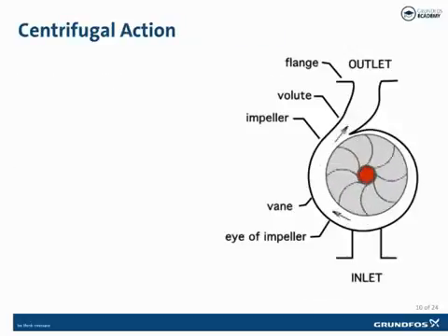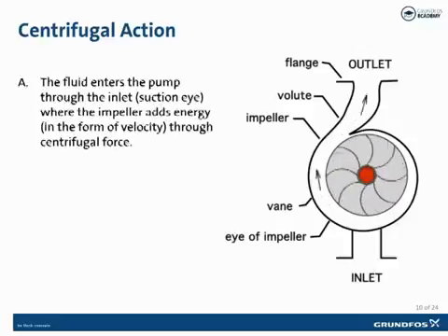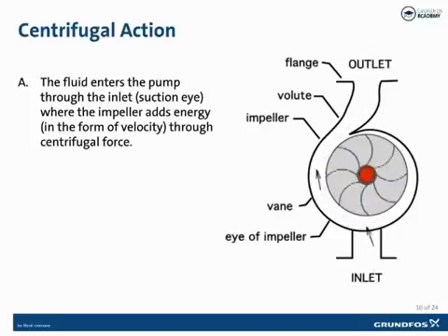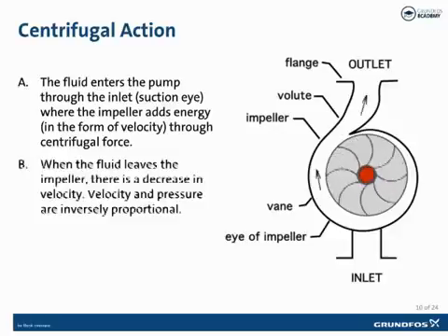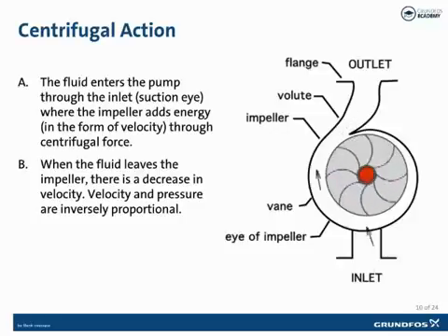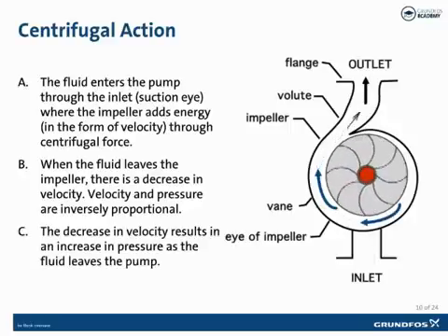This picture explains the operation of the centrifugal pump, showing the volute and the impeller working together. The fluid enters through the inlet of the volute through the eye of the impeller, where the impeller adds energy in the form of velocity through centrifugal force. When the fluid leaves the impeller, there is a decrease in velocity. Velocity and pressure are inversely proportional — as velocity increases, pressure decreases, and as velocity decreases, pressure increases. The decrease in velocity results in an increase in pressure as the fluid then leaves the pump.